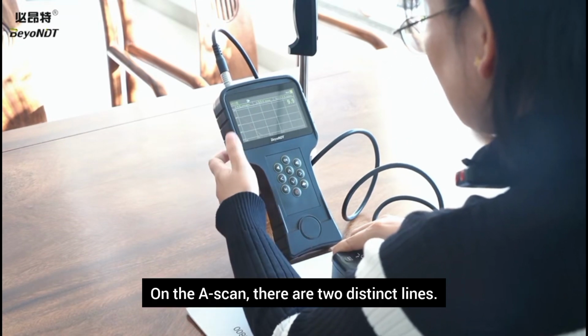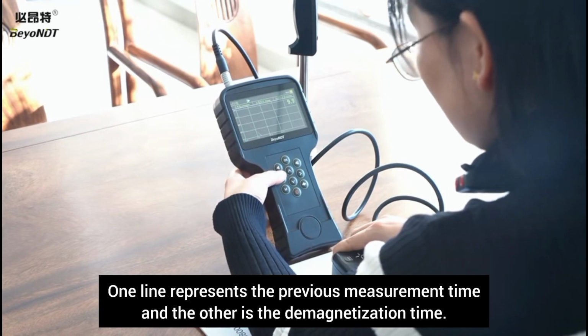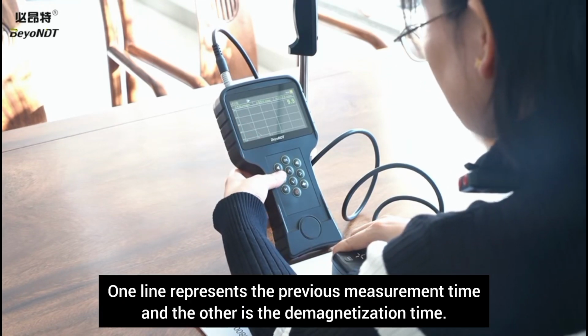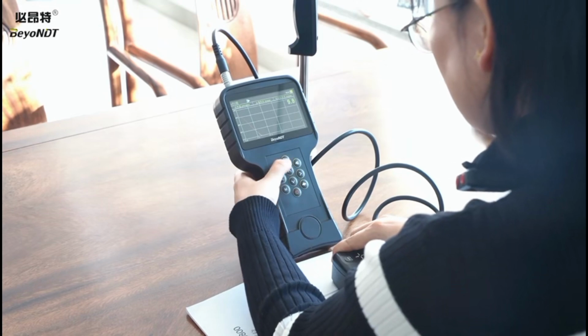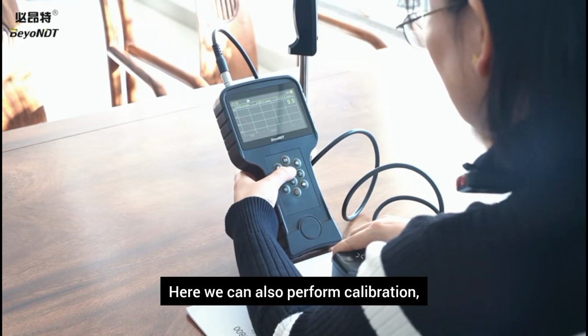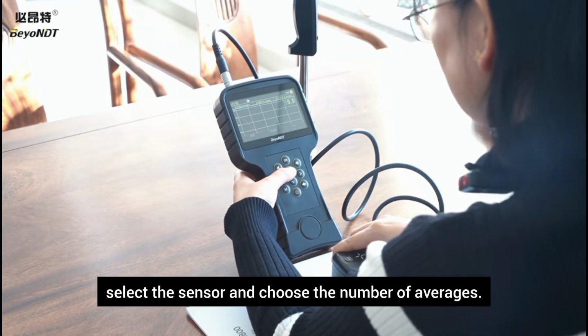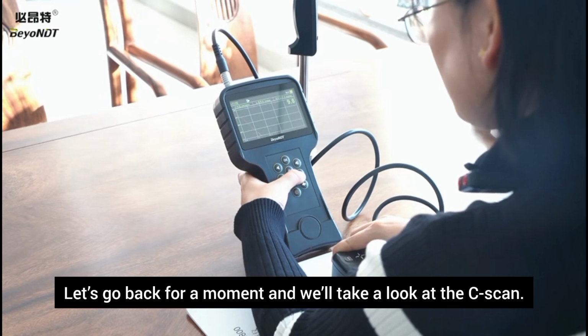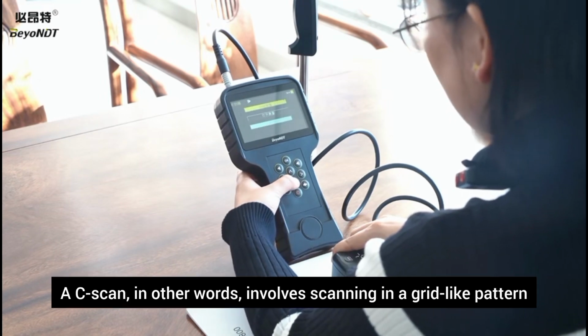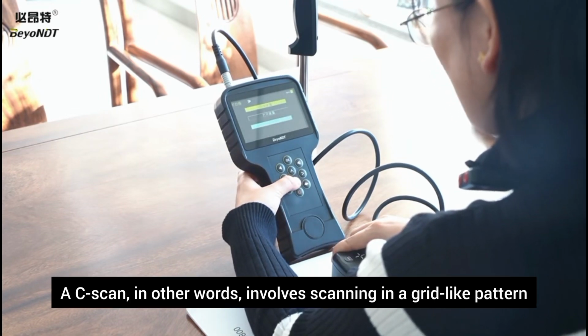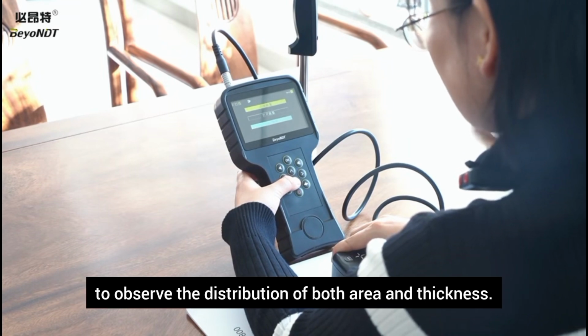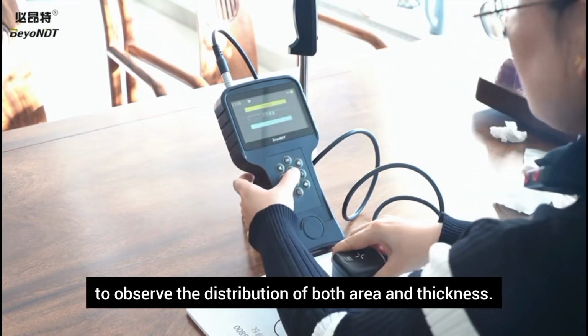On the A-scan, there are 2 distinct lines. One line represents the previous measurement time, and the other is the demagnetization time. Here, we can also perform calibration, select the sensor, and choose the number of averages. Let's go back for a moment and we'll take a look at the C-scan. A C-scan, in other words, involves scanning in a grid-like pattern to observe the distribution of both area and thickness.